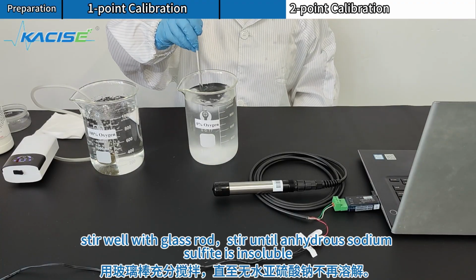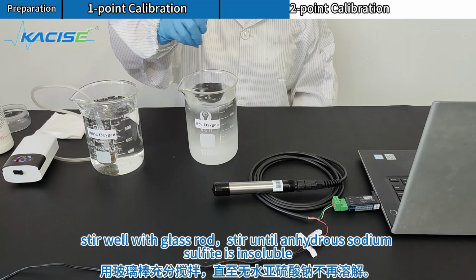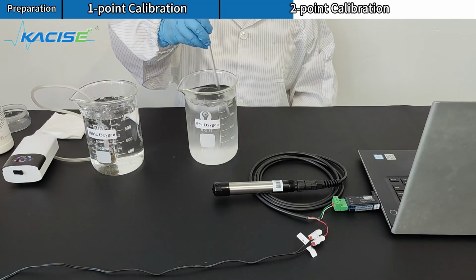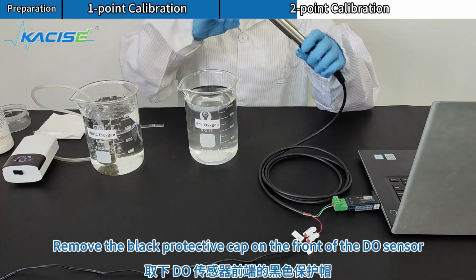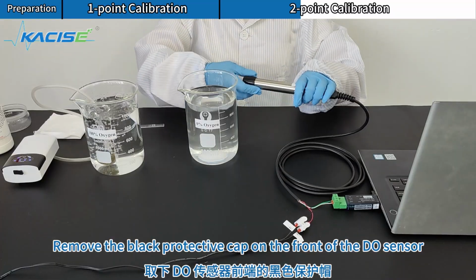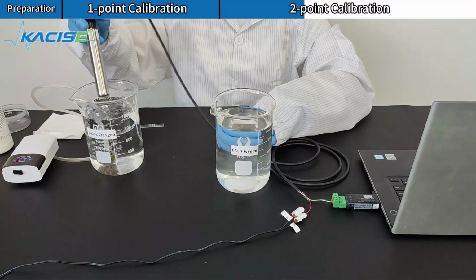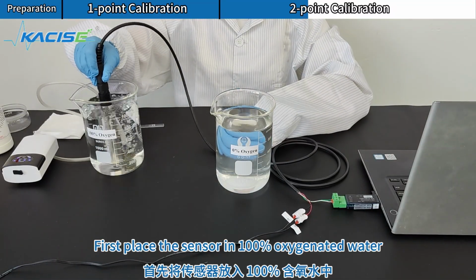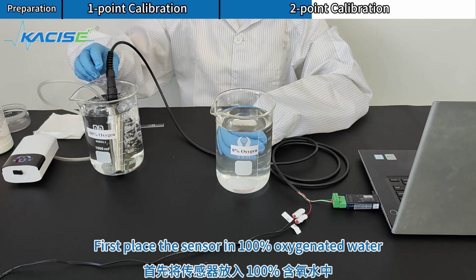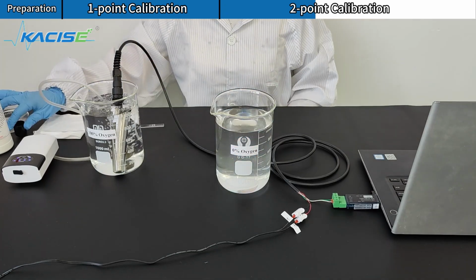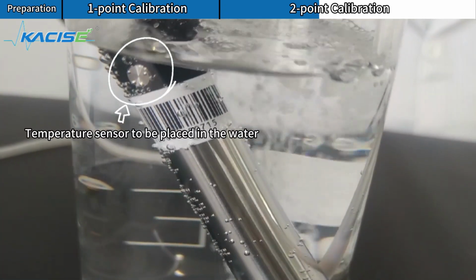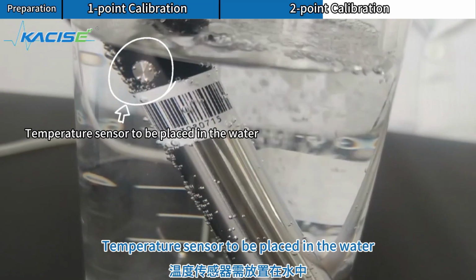Stir well with a glass rod until the anhydrous sodium sulfite is dissolved. Remove the black protective cap on the front of the DO sensor. First, place the sensor in the 100% oxygenated water. The temperature sensor is to be placed in the water.